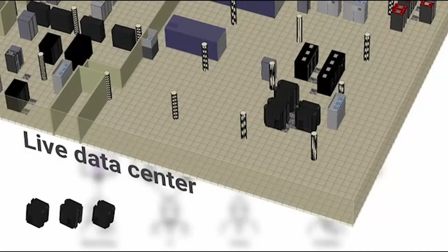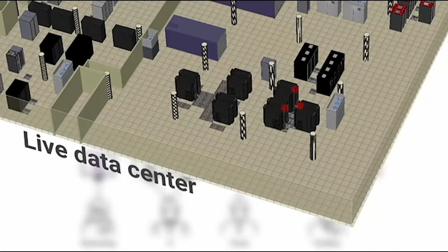Because of this, when the equipment is installed, our invisible enemy, airflow, takes matters into its own hands. And what we actually see is thermal alarms going off on the equipment that's located in the next row over from the new deployment.